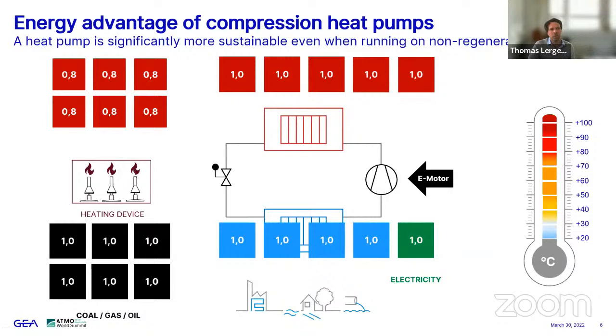So this is an important balance: how efficient a heat pump is, how many units of heating energy you get per unit of input power, electricity. That depends a little bit on the temperature level, but the relation is expressed by the COP, the coefficient of performance, which is your heating energy divided by the input power, the electricity in this case of our compression heat pumps. That COP, this ratio, is typically between 3 and 6, depending on the temperature difference and the temperature lift.